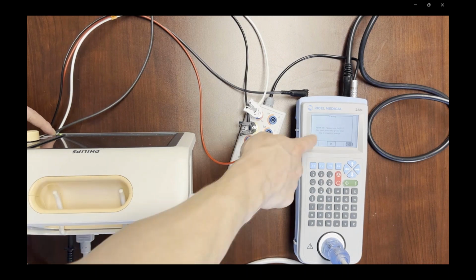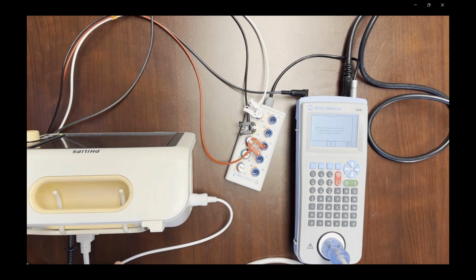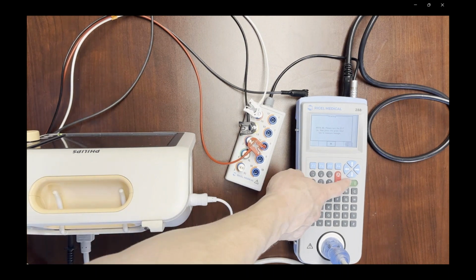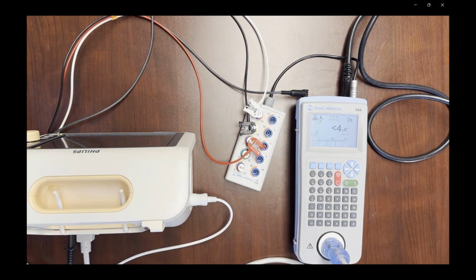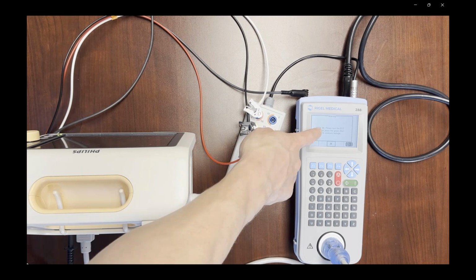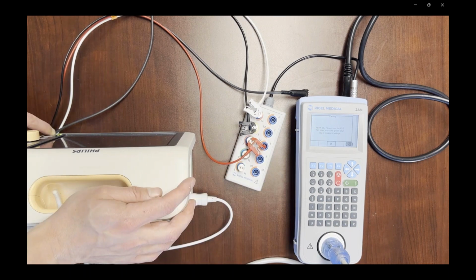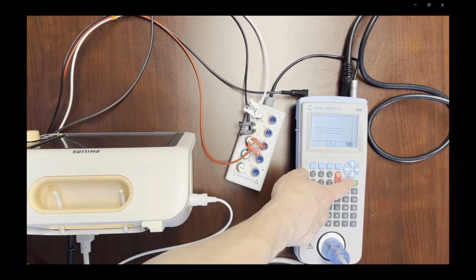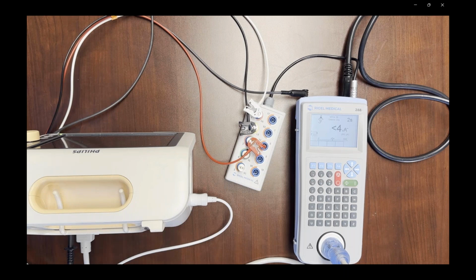So long as everything's okay and it's running correctly and all the measured values are within specification, then it will proceed to the end of the test and give you an option to key in the report. And those prompts on there tell you to turn the device on and off according to the NFPA 99 code.